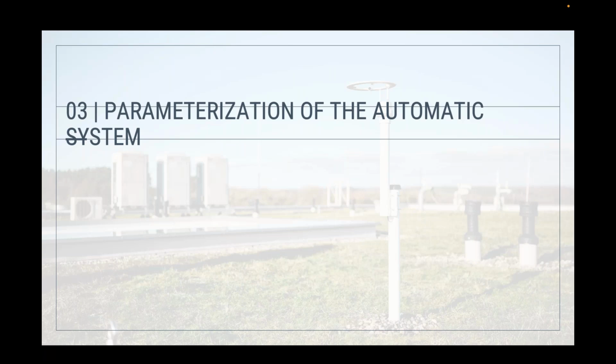If you're trying to automate a shading system for a building that, let me say, is G+5, so ground floor plus 5 more stories, then it is required to have at every 3 stories, that's at least our recommendation, to have an external wind measurement sensor, and this one should be electronic, because the higher the buildings, the more likely it is that you have uplifting winds. Just from the way the sensors are designed, a mechanical wind sensor will never be as strong at detecting uplifting winds as an electric one is.